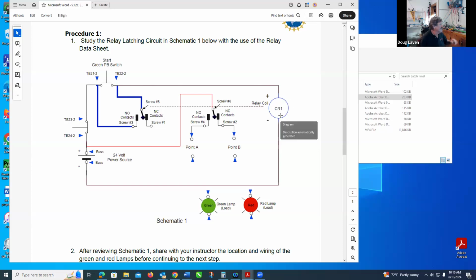But the interesting thing is, I'm holding this button down. This has swung over, but when I release this, guess what? Power is now coming from the power supply through here, around the switch, and it keeps the coil latched up or energized, and that's what latches it up. So you're basically putting a normally open set of contacts in parallel with your normally open push button switch. And that's it. That's the magic. That's a motor starter. That's a latching circuit. It's as simple as that.